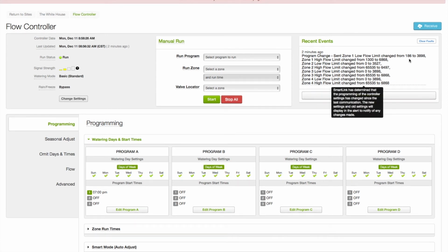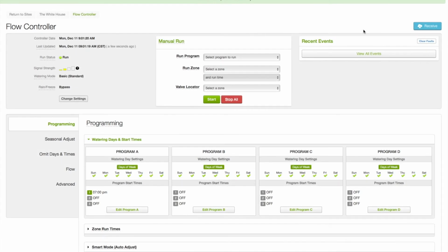Okay, so we can see that these flow rates have changed. These are actually not the volume in gallons, so don't be worried about this. This is actually the flow pulses, the raw flow pulse data number, so don't be disturbed if you see that. So let's see if we can get that flow error to come back. Okay, so our receive came through. Our flow event went away.